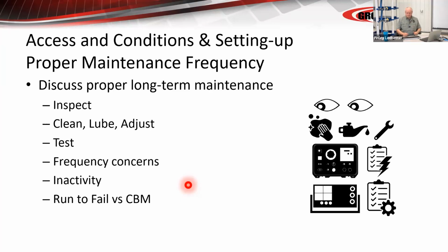But basically what happened is the testing went from 1 to 2 to 3 to 5 to 7 to 10 years. That's pretty much the way that the maintenance cycles adjusted. When I first got into the business, everybody was pretty much at 1 year, particularly the Bell companies and heavy industry. Then they started skipping a year and doing some secondary checks and some random checks of individual equipment based on criticality, then to 3 years, then to 5, then to 7. Now some people are looking to go to 10.